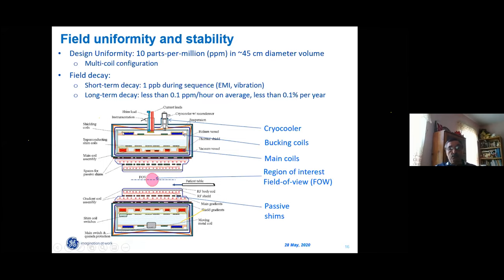We also use so-called shielded coils to compensate stray magnetic field. Field decay. There are two requirements. First of all, during scanning, field decay or field variability shall not be more than one part per billion. And the long-term effect is 1/10 of a ppm per hour on average, which means that standard MRI magnets lose no more than 1/10 of 1% field per year.